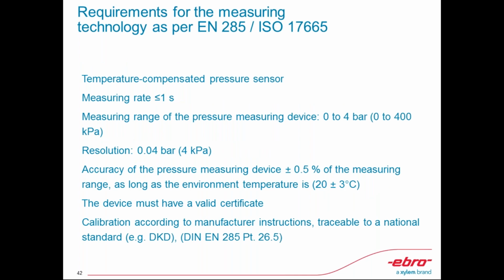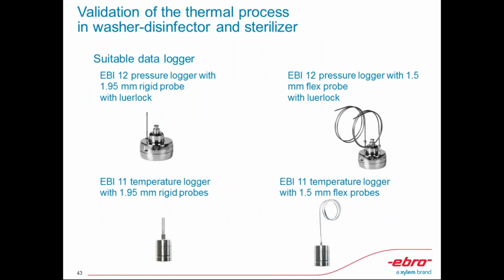So still according to ISO 17665, you will see here the importance of measuring pressure in your processes, because not only is pressure directly proportional to temperature, but it's also very much a factor for heat penetration and keeping the equilibration time criteria.